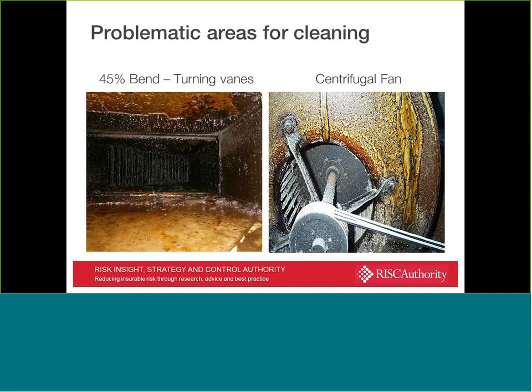Problematic areas for cleaning include turns in the ductwork. You can see an example on the left-hand side of a 45 degree or a right-angle turn in the ductwork, where turning vanes have been installed to help the airflow to move, but all that does is increase the volume of grease and oils that are collected. Or similarly on a centrifugal fan, where in this circumstance oils and grease have been allowed to accumulate quite significantly.